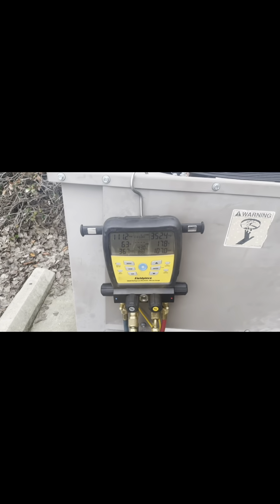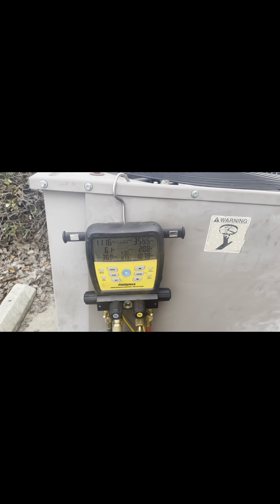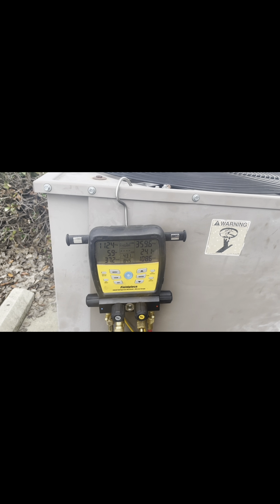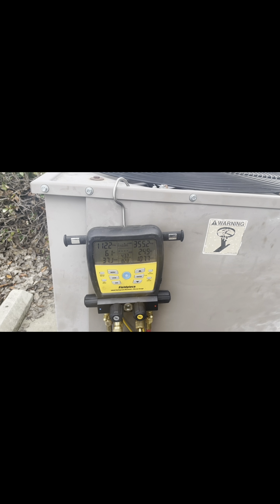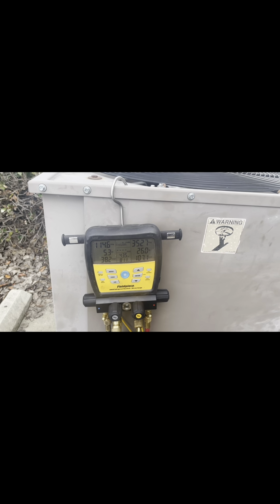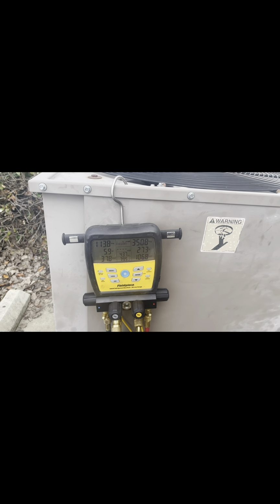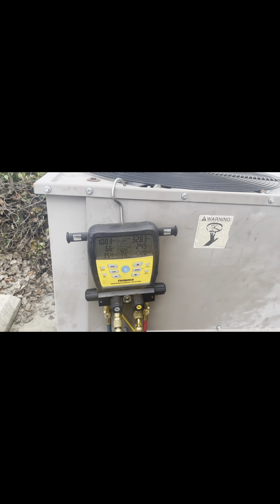Running at about 107, 108 degrees liquid saturation. That's pretty damn good. These are both compressors running right now. Let's go inside and check our supply air, and then we should be good to go. 75 degree return, 52 degree supply. I'd say we're good.